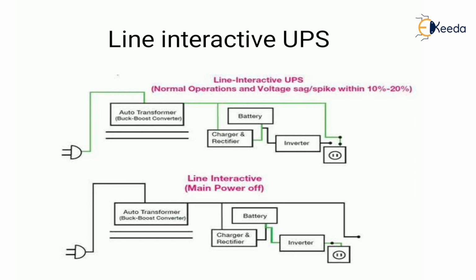They provide a high level of protection at an affordable price, and this category resembles an offline UPS, but it inserts a transformer, or you can say an inductor, in series between the utility power source and the load. This inline inductor enables the UPS inverter to interact with the incoming power and provides a measure of power conditioning to the load, and this buck boost circuitry helps in the high and low input voltage conditioning. So this is about the line interactive UPS.